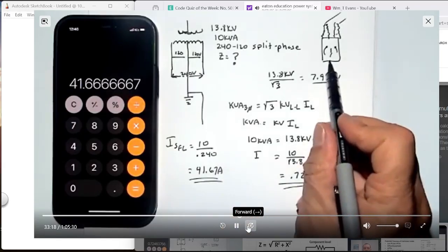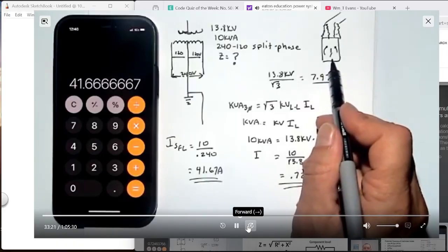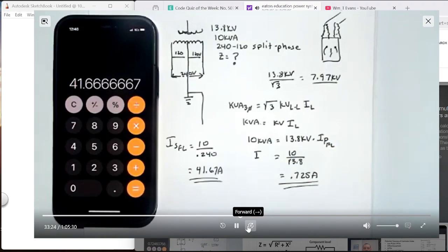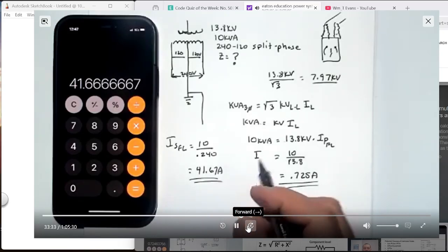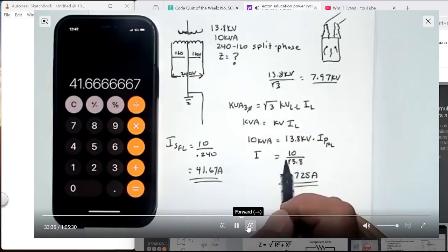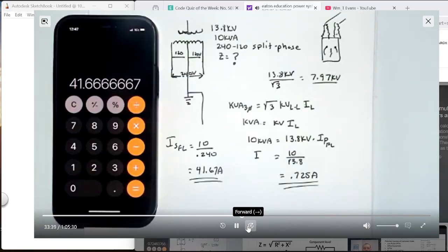But the utilities actually will push these transformers up even more, and they'll let you draw through maybe almost 2 times the normal kVA because they'll just let them blow off the poles. But the reality of it is you're never going to approach the 200 amp panel that's in your house. So why do we put 200 amp services in? Well, we don't know. If they have a 10 kVA transformer, they may upgrade that to a 25 kVA transformer or maybe 50 kVA. So we don't know. And so the capacity of the service coming into your house is what really dictates your breaker and not necessarily the full load amps in this case. Everybody get that? At a 10, that's all they give you, is 41 amps.